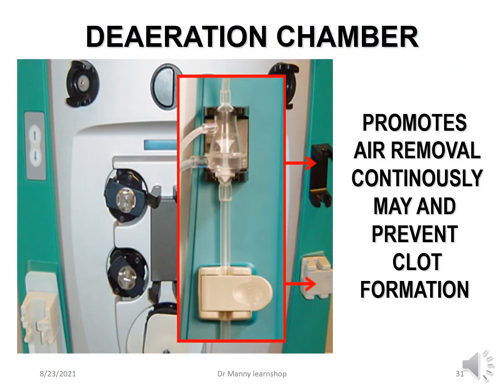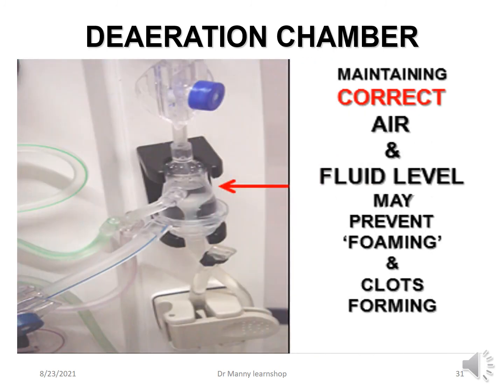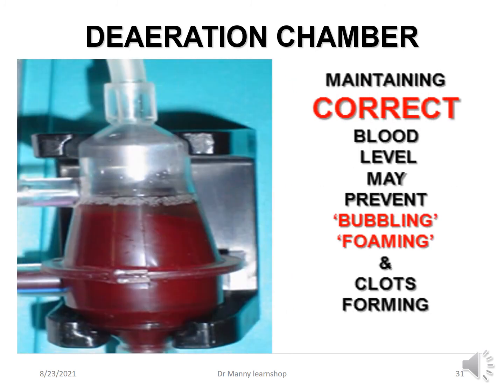Then you've got the deaeration chamber, which promotes air removal continuously, and in doing so, stops bubbling. Air in the chamber can cause bubbling, and this may prevent clot formation. In the deaeration chamber as well, it's important that you maintain the correct air and fluid level, because again, this prevents bubbling or foaming, and in doing so, it obstructs blood flow. And if it obstructs blood flow, clots can form. So it's important that fluid levels are maintained as per the recommendations. There's a good example of where the fluid level should be, and there doesn't seem to be any bubbling there at all. So maintaining the correct blood level may prevent bubbling or foaming and clots forming.